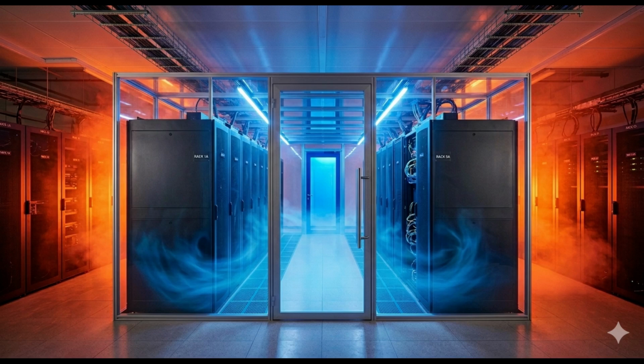Let's break those variables down because this is the key to everything. Q dot is the heat load. Yes, Q dot is the total cooling capacity, usually measured in kilowatts. It's the rate of thermal energy being generated by the servers that we have to extract. And rho? Rho is the density of the air, kilograms per cubic meter. This is an environmental variable. A data center at sea level has higher air density than one in Denver, which physically changes the mass flow of your cooling medium. Okay, and then V dot, that's the volume.